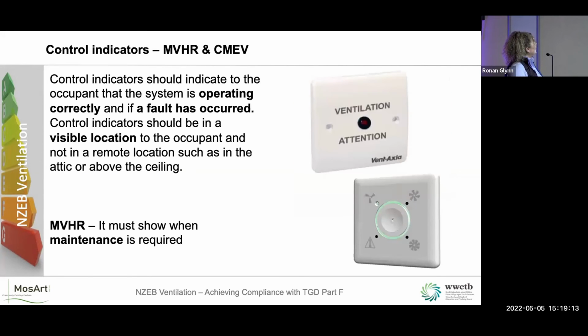Again, control indicators. They must indicate to the occupant that the system is operating correctly or if a fault has occurred, and control indicators should be in a visible location. So when Part F came out first, there was a big scramble, especially on CMEV units, the likes of Airco, were trying to get control indicators for their machines. It shouldn't be in a remote location, so it should be wired down into your kitchen or living room or somewhere where you can see it.